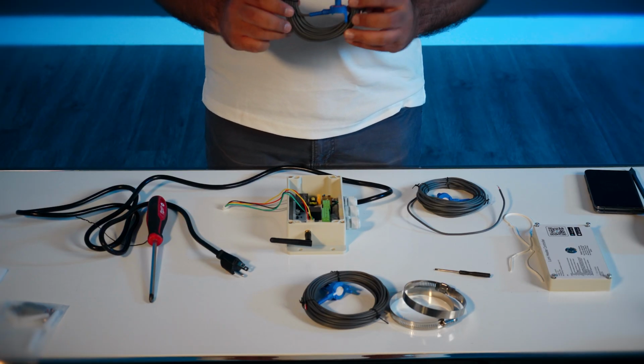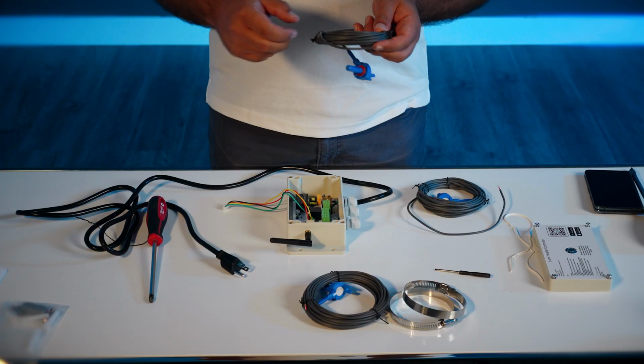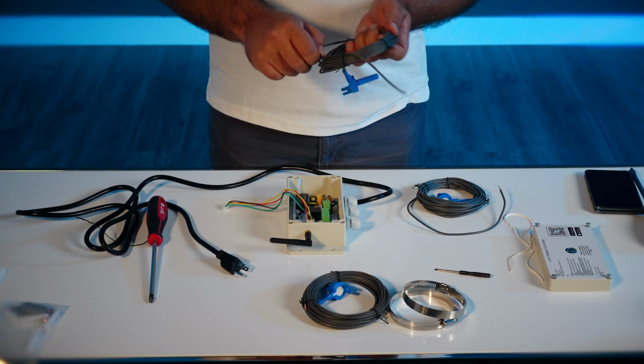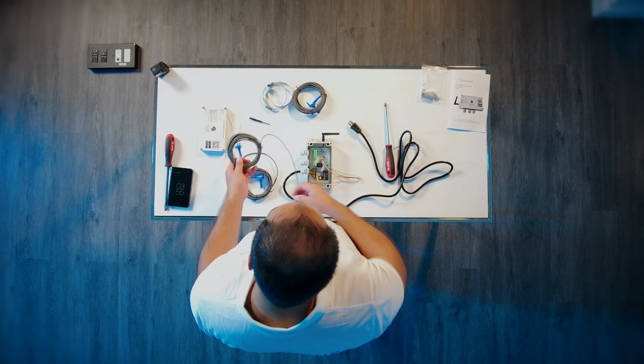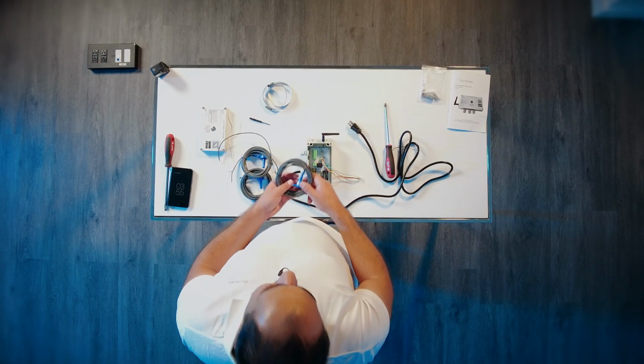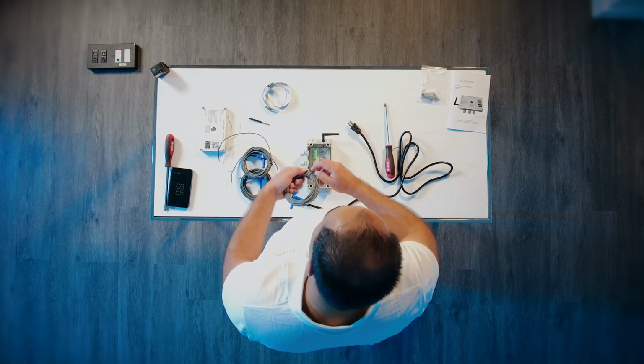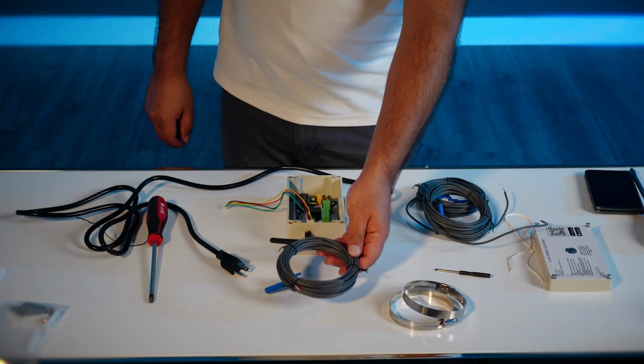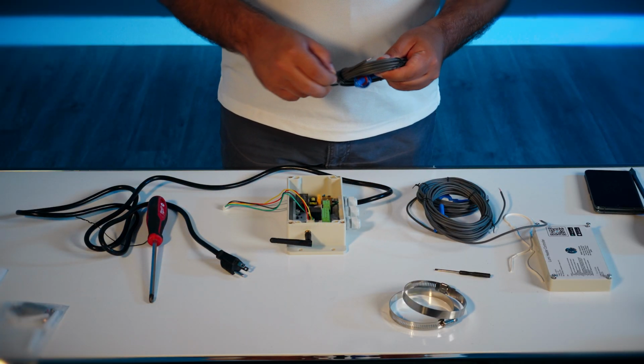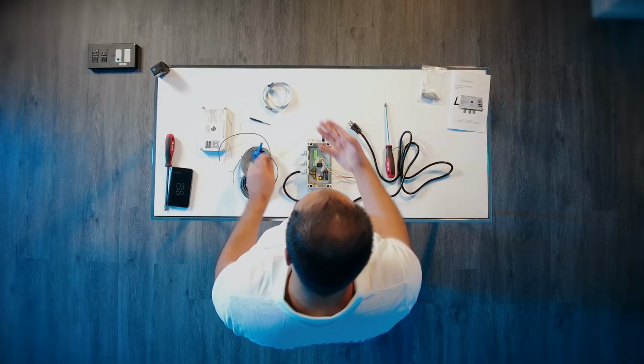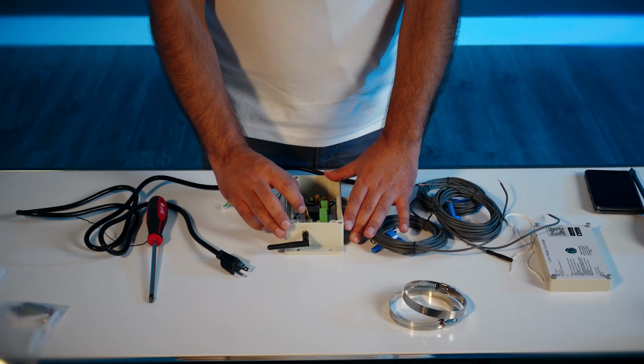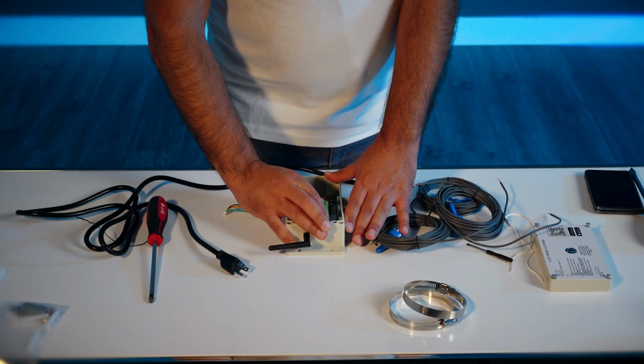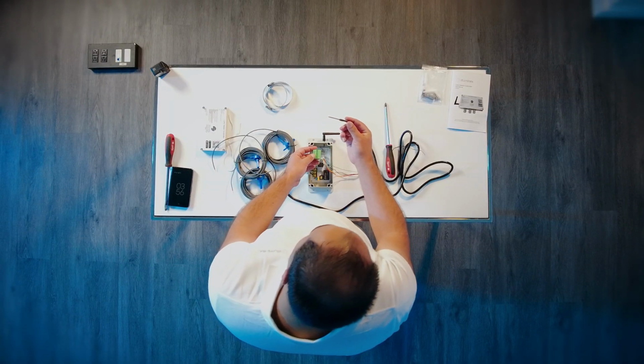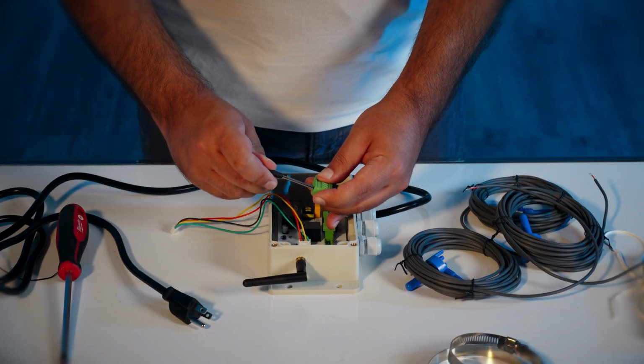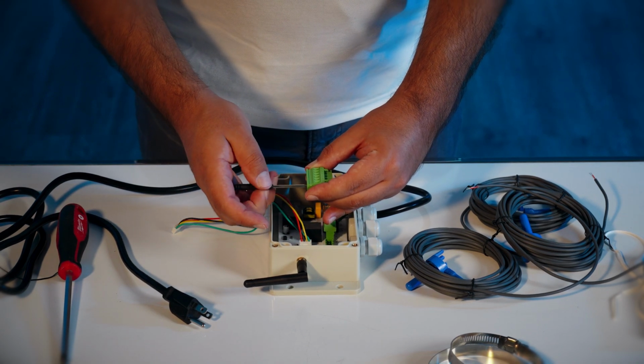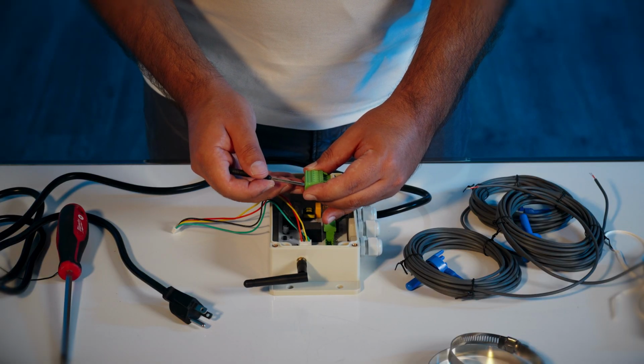So first, we're going to open up the temperature sensor cables. Normally, these would be installed in the heater inlet port and the heater outlet port. And the last one is for ambient air. That one gets installed where you have fresh air so you can record the ambient air temperature. So we're going to open the cable for this one also. Just a little bit. Now, next, the 6-pin terminal wire. Just give it a little wiggle. Comes out of its spot. We supply you a small screwdriver. Open up all the ports. So you can see as you open it, the flap moves down.